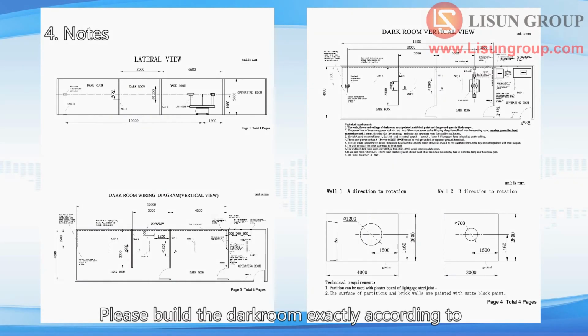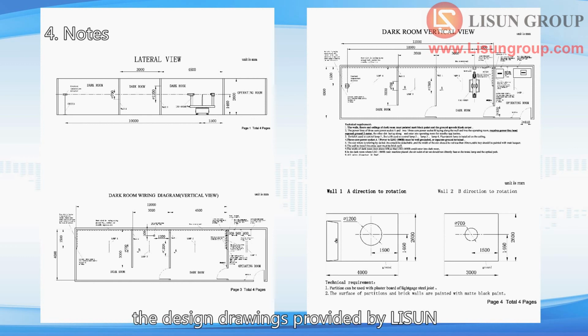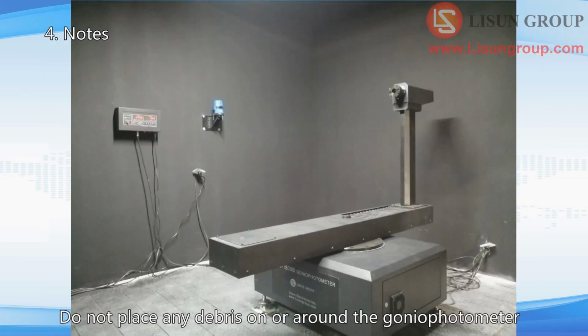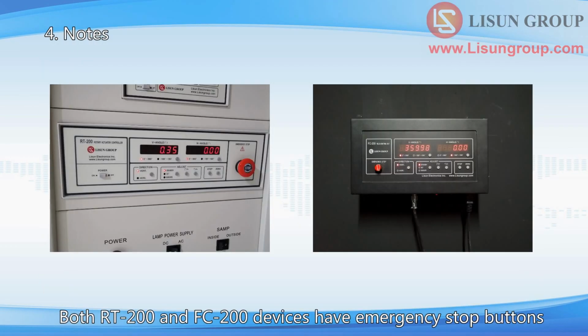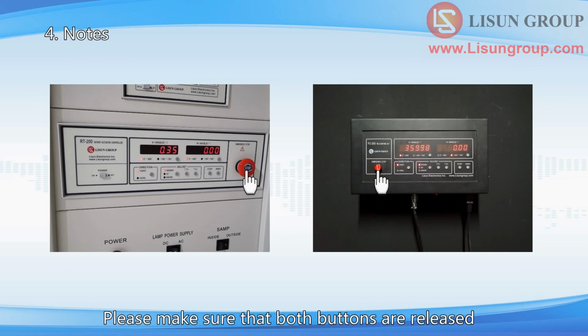Please build the darkroom exactly according to the design drawings provided by LISUN. And note that the paint is matte black. Do not place any debris on or around the Goniophotometer. Both RT200 and FC200 devices have emergency stop buttons. Please make sure that both buttons are released when you use the Goniophotometer system.